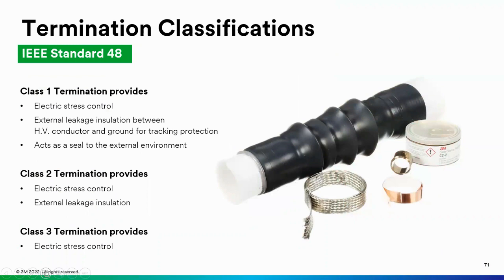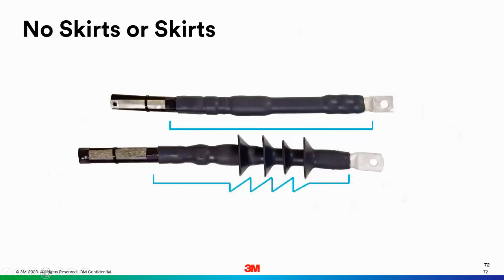All of our terminations are class 1, which meet these standards that you see here. So it provides electric stress control, provides tracking protection, and is sealed off to the environment. Here you'll see two different types: an indoor termination on the top and an outdoor termination on the bottom. The bottom one, the outdoor termination, is skirted for several reasons. Some people call them rain shields, which allow the water to drip off, which they do, but it also increases the creepage distance, or the leakage distance. So you see the blue line is one length in the indoor, but it's much longer in the outdoor. That makes the termination much longer for that purpose, so you have a much longer outdoor termination.